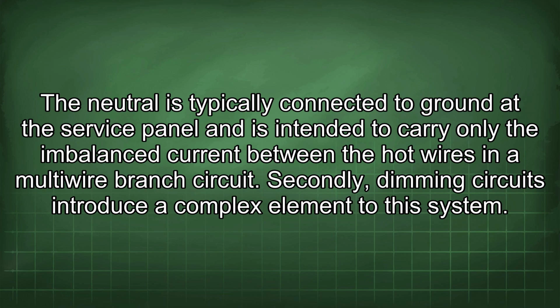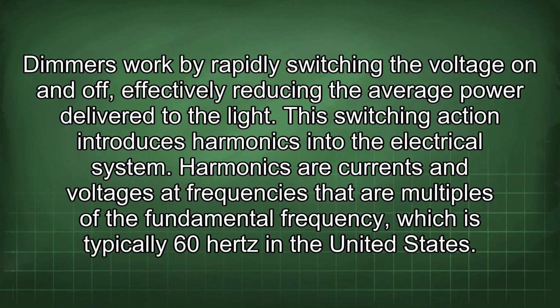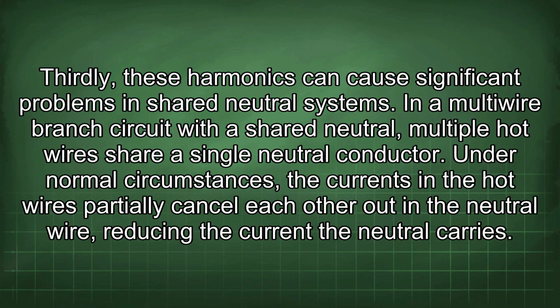Secondly, dimming circuits introduce a complex element to this system. Dimmers work by rapidly switching the voltage on and off, effectively reducing the average power delivered to the light. This switching action introduces harmonics into the electrical system. Harmonics are currents and voltages at frequencies that are multiples of the fundamental frequency, which is typically 60 Hz in the United States. Thirdly, these harmonics can cause significant problems in shared neutral systems.